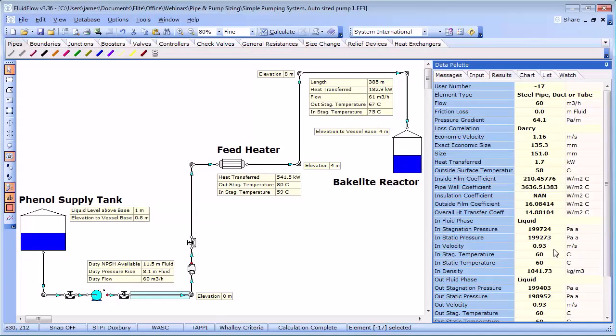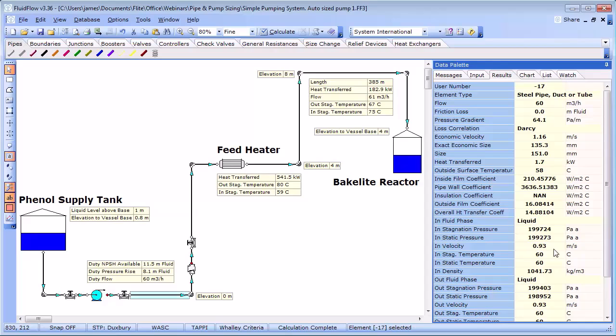The size you choose will depend on your circumstances. Some factors you may wish to consider might be the future likelihood of increasing capacity in the system, existence of a subset of standardized pipe sizes in your organization, intermittent or 24-7 operation, erosion, particle settling etc. In this case we are going to proceed with 150 millimeters. This means we are now ready to complete the system loss calculation which determines the total head required by the pump.